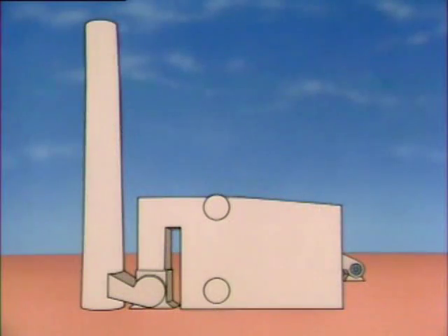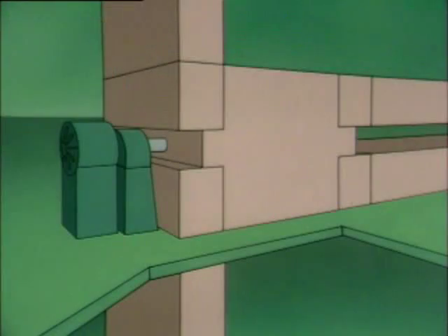The mixture of fuel and air supplied to a boiler is called the fuel-to-air ratio. It's important to maintain the proper fuel-to-air ratio to avoid combustion problems. For example, if the boiler is not getting enough air, some of the fuel entering the boiler won't burn. Instead, it may get carried out with the combustion gases and wasted. In some cases, unburned fuel could build up in the boiler. This buildup could cause an explosion if the fuel were ignited.